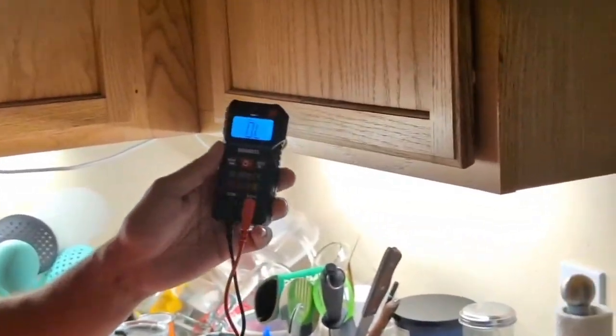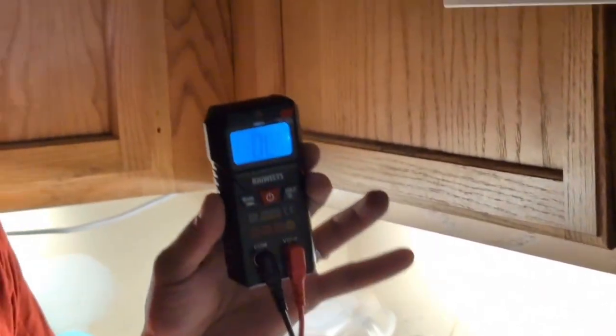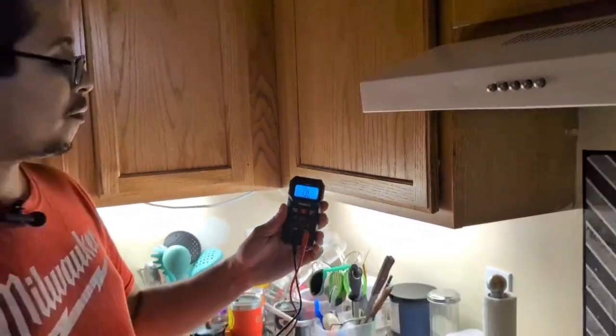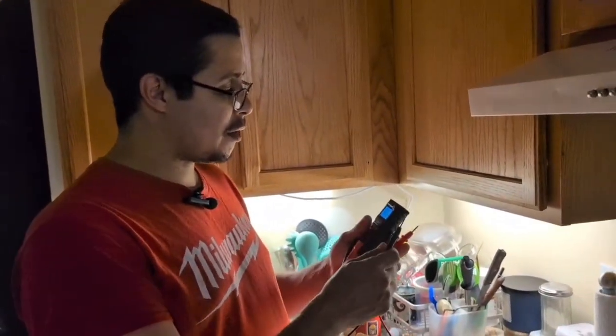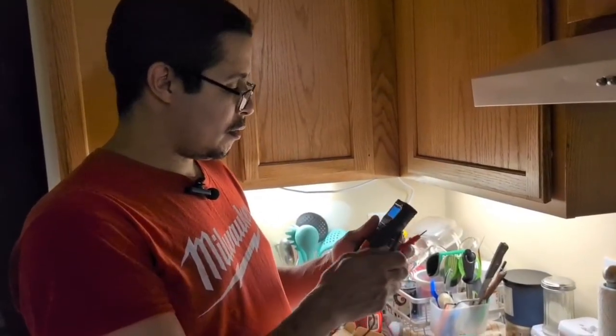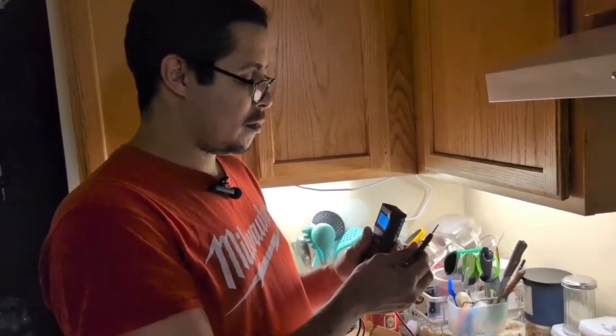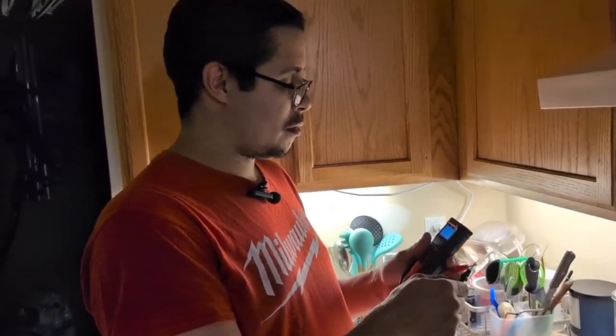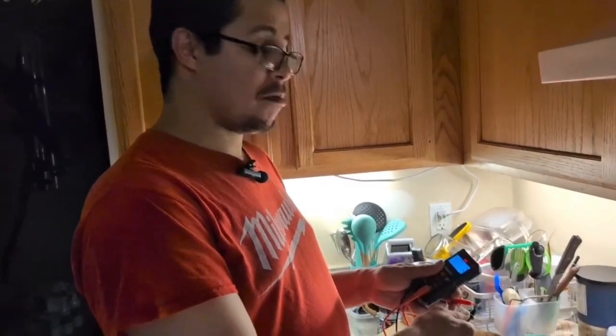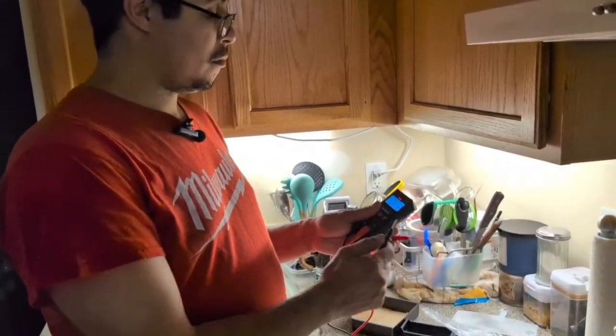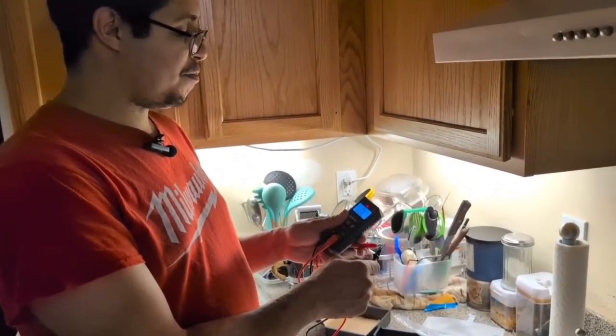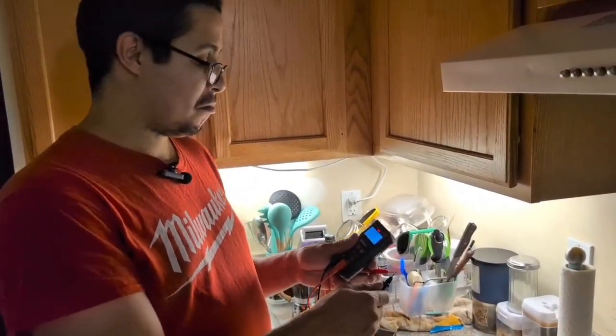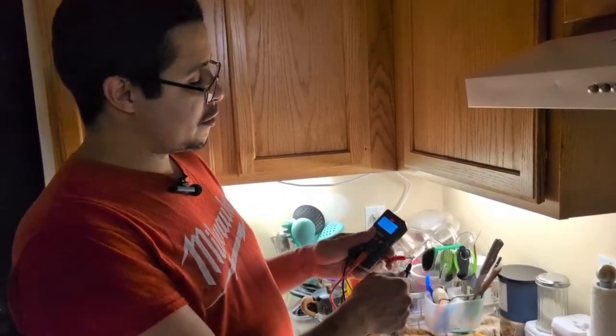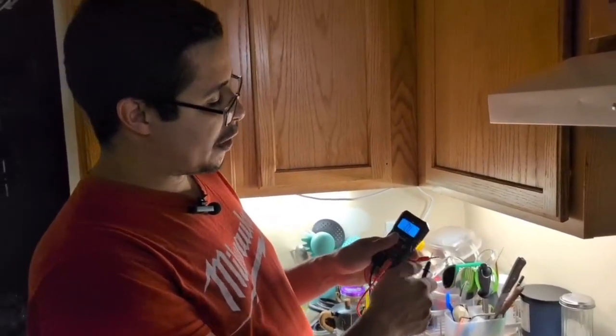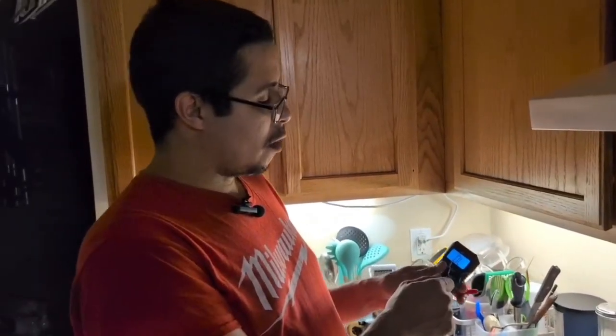Then we have continuity. Now continuity mode is very, very good when it comes to troubleshooting. Let's see how it tones out. Oh, hold on. Not bad, that's pretty loud. Bit of a delay though, but it's not bad. As you can see, it's also taking an ohm reading as well. You see OL, over limit.